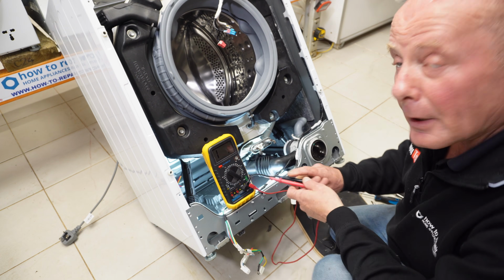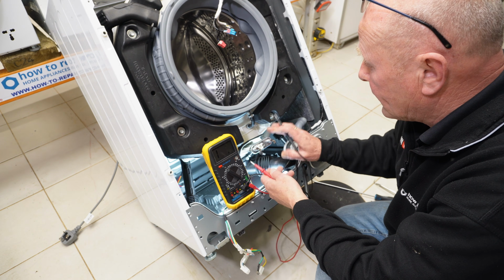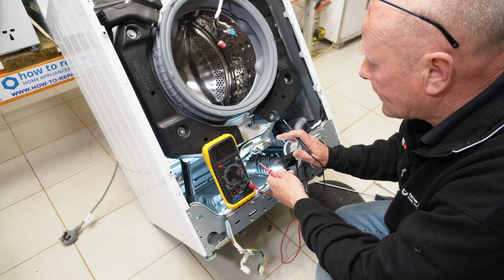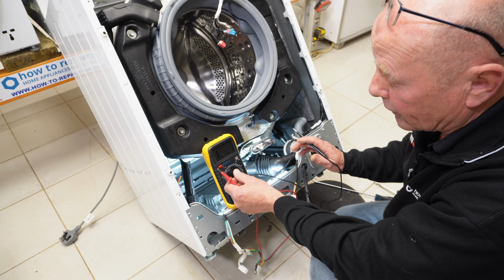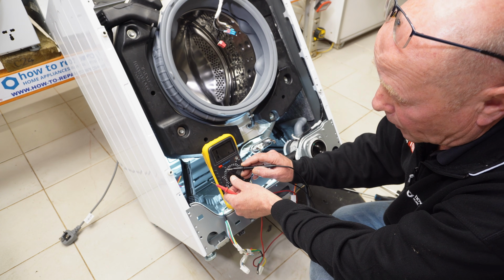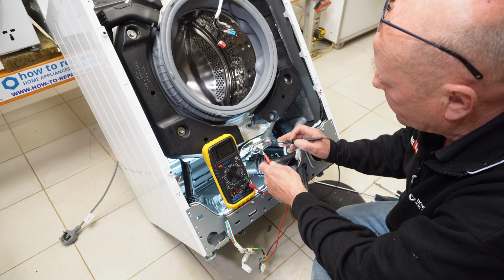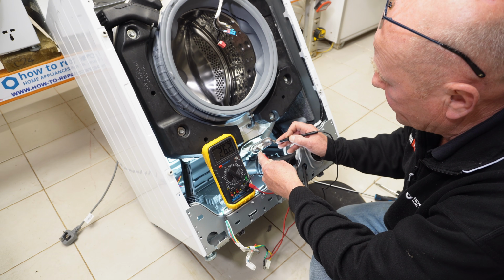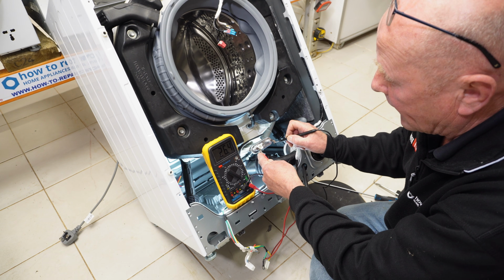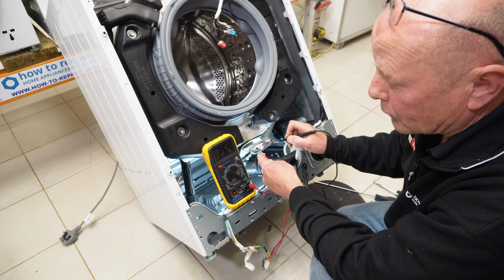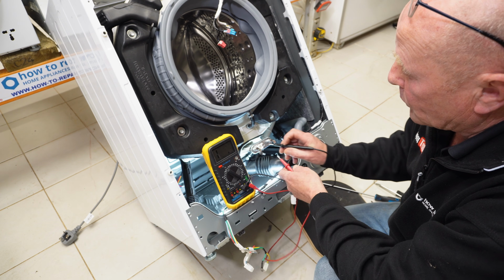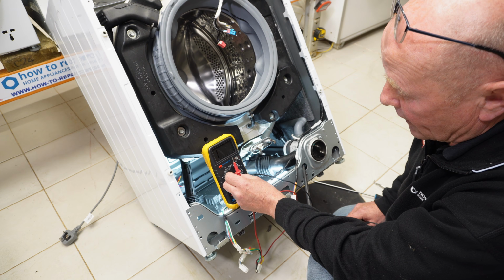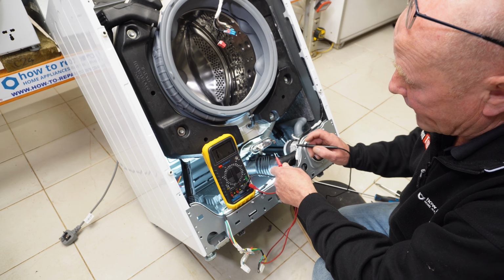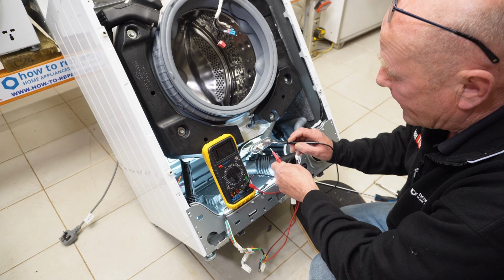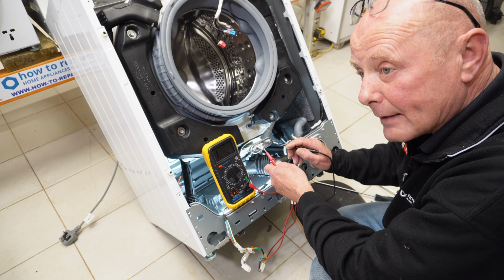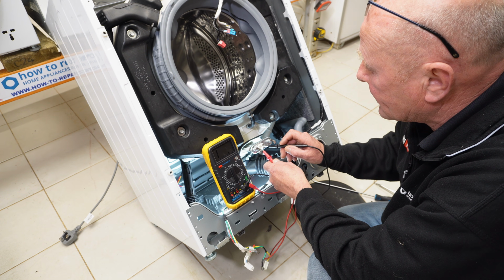Okay, I just thought this might be useful for some people. This is a brand new element and NTC sensor because this is a new machine I'm working on. So setting your multimeter up onto 200 range on ohms and going across the element, because the element is a 2 kilowatt element, we have an ohms resistance of 26.4. And if you want to check the NTC sensor, this is a different thing altogether. We've set it to 200K range and we've got an air temperature of approximately 15-16 degrees.